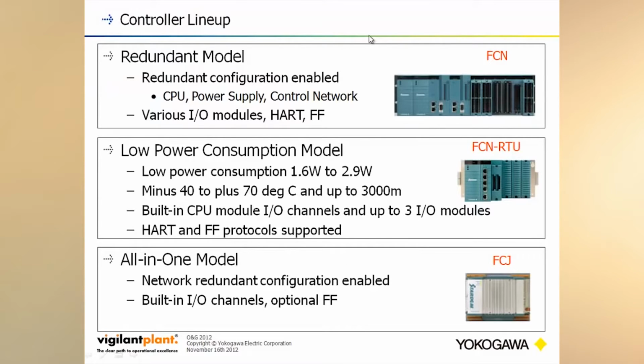Stardom consists of three different models. The first is for high reliability situations. We can support redundant power supplies, redundant CPUs, redundant field bus communications, redundant serial communications. The only thing we can't do redundantly on this is straight redundant I/O. We include communications to various smart protocols for I/O, such as HART and Foundation Field Bus on this unit.